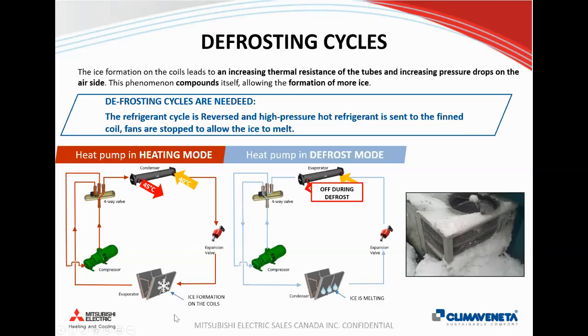There's standard defrost, which is really just based off fixed timers in the control logic for the heat pump. And it's using the evaporating pressure as an indicator of having frost or ice built up on the coil. So basically, if your evaporating pressure on the refrigerant circuit decreases below the programmed value inside the machine, after a fixed countdown timer, it will eventually say, okay, we need to defrost, and we'll switch the machine into a defrost logic. With fixed timers, it's rudimentary in a sense, and the heat pump doesn't have eyes. It can't really see how much ice or frost is built up on the coil. So it's just using fixed timers and hoping that it melts off all the ice.